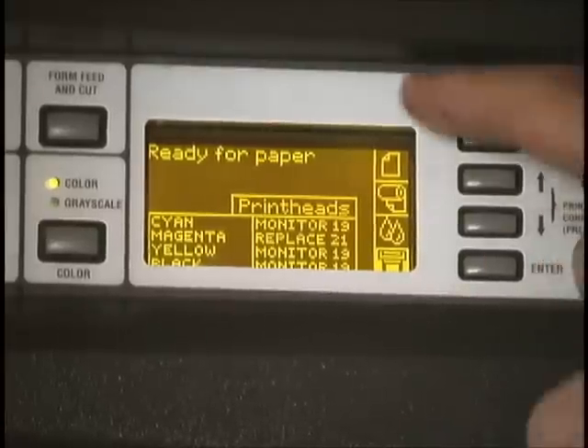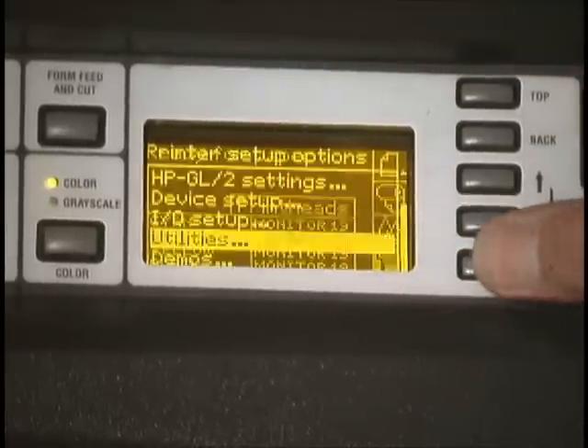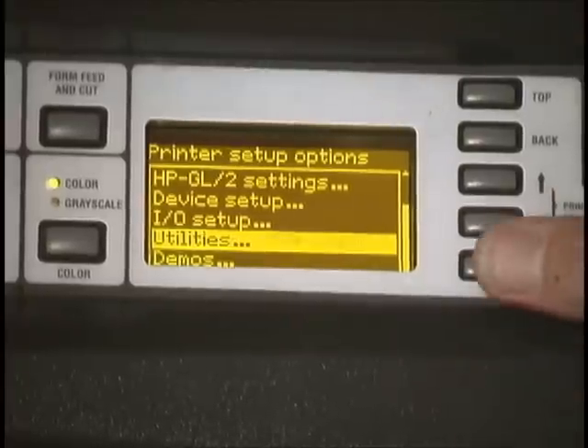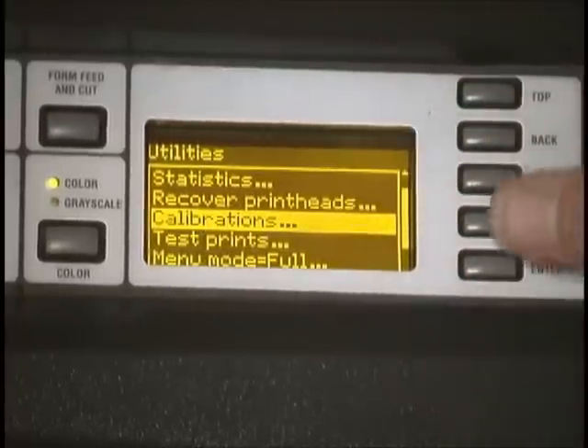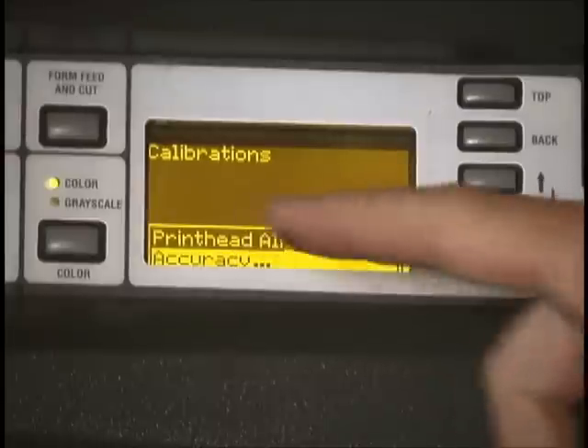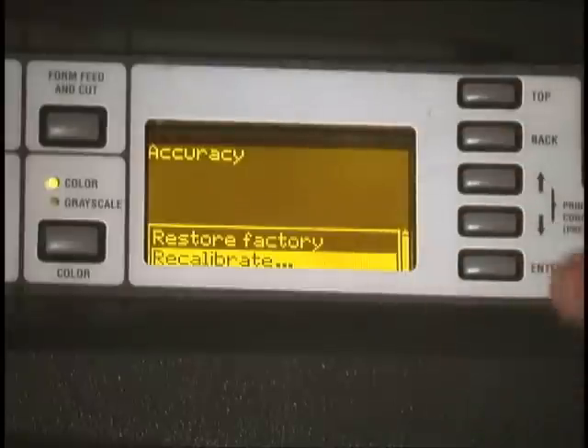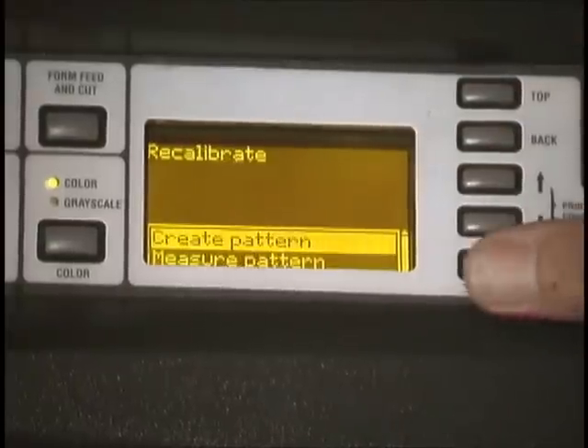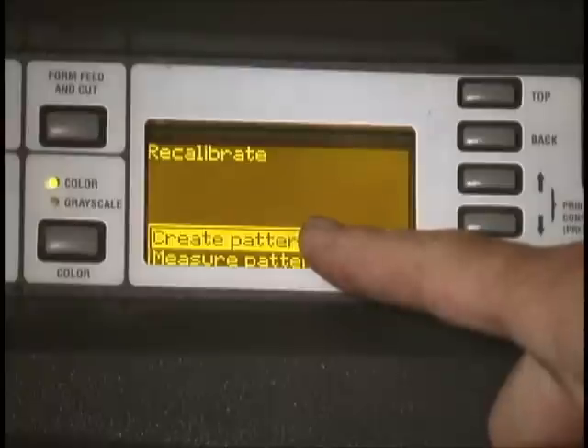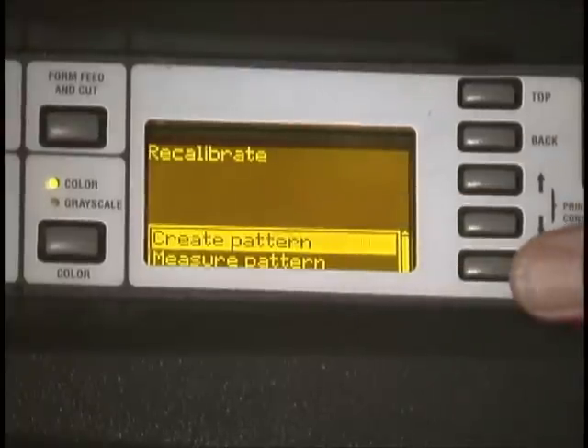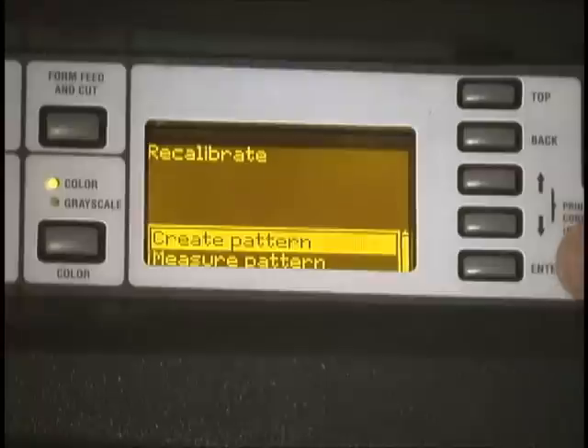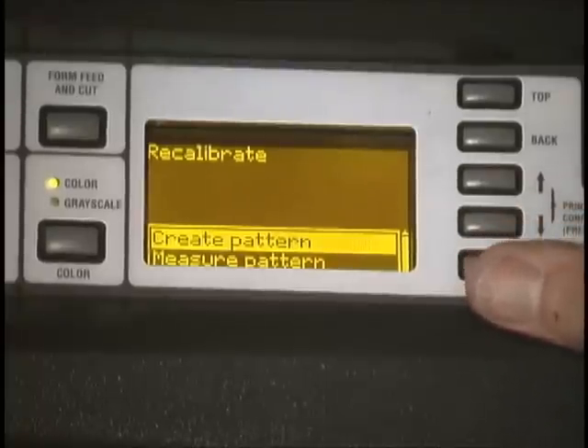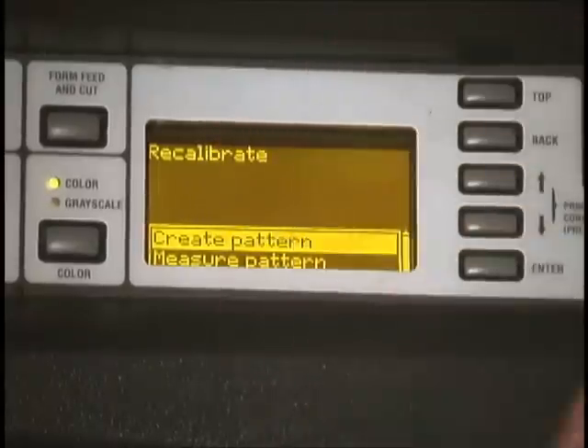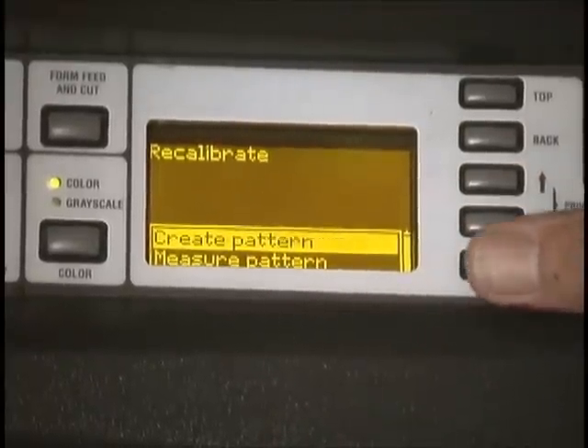The way to get into this menu is to go to the main setup menu. We're going to choose Utilities, and in the Utilities menu, Calibrations, and in Calibrations we're going to choose Accuracy. We press that. We restore factory defaults, but that's not where we are anymore. We don't want to do that. So we're going to recalibrate, and we're going to create a pattern. Here's where we're going to use the polyethylene film that was in the kit. So I'm going to hit enter. This is going to go through a rather lengthy process where it is making some internal measurements, and eventually it will come back and ask for paper. I'll come back at that point.